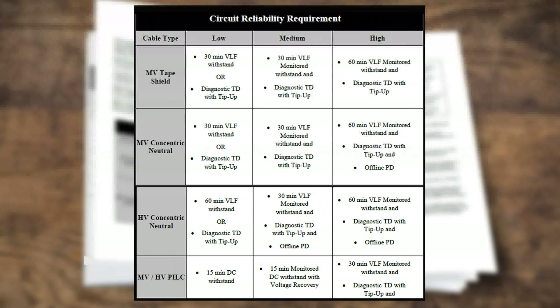We further break it out by cable type. How you'd treat a medium voltage tape shielded cable would be different from how you'd treat a concentric neutral or potentially an oil impregnated PILC cable. Each has its own nuances when it comes to what type of test works best, and that guidance is given in the new NETA Appendix D.